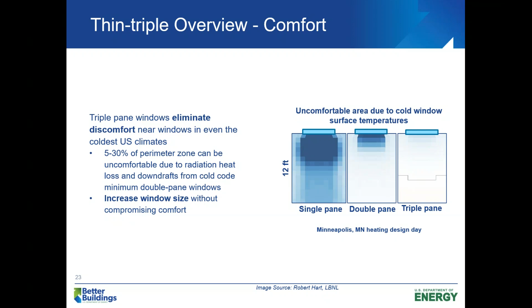When we look at a commercial building, we're also thinking about a holistic, systems level approach. By putting in a high performance glazing, such as the thin triples, we can eliminate the perimeter zone in many buildings. We have to do some energy modeling to prove that, but by eliminating that perimeter zone heating, you're saving a significant amount economically, and it also allows you to downsize the HVAC system, so you don't need as much heating or cooling capacity. There's really a systems level perspective here that we want to approach.